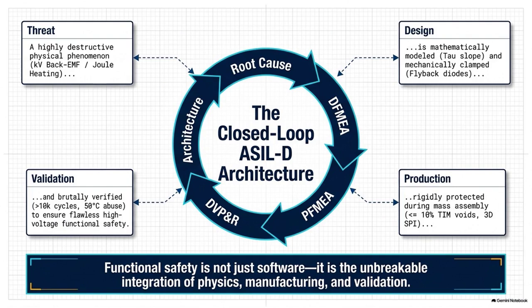If it passes, the system generates a cyclic redundancy CRC32 checksum based specifically on the physical parameters validated during that test. It writes that foolproof digital signature directly into the non-volatile memory of the BMS. No checksum, no leaving the factory. It's a digital wax seal, cryptographically binding the physical hardware's verified performance to the software's boot logic. The sheer depth of the paranoia is just staggering.